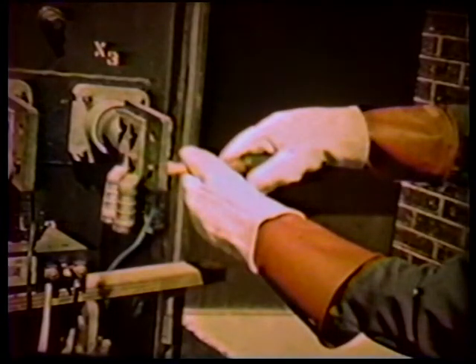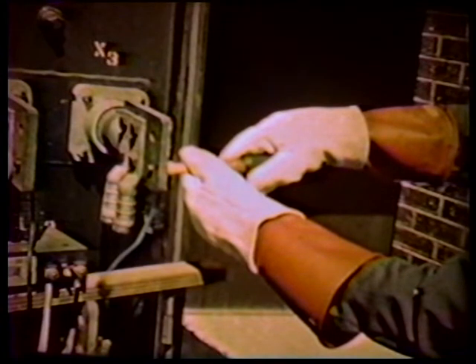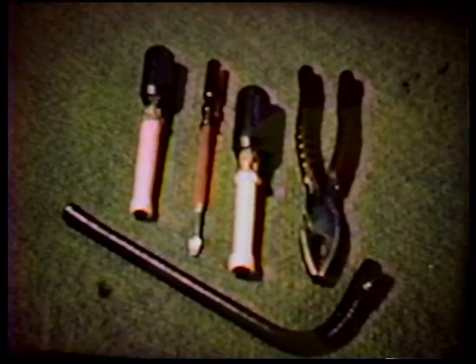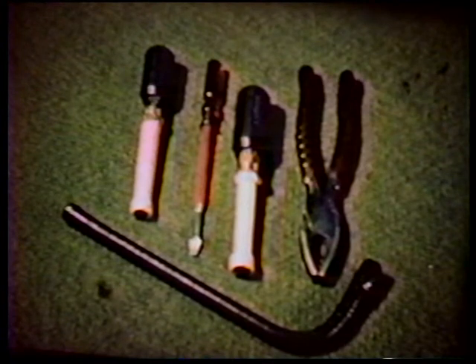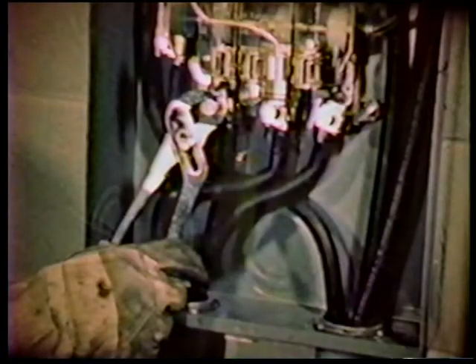Low-voltage rubber gloves are designed primarily for metermen to protect them from electrical shock. These gloves are periodically tested and should be inspected before use. The light leather protectors should always be worn over the rubber gloves. A variety of insulated tools, if used properly, can protect the user from accidental contact with energized parts. No, not those water pumps. Use the insulated socket wrench and make sure it is in good condition, with the insulation intact.